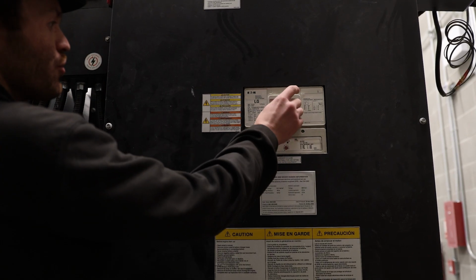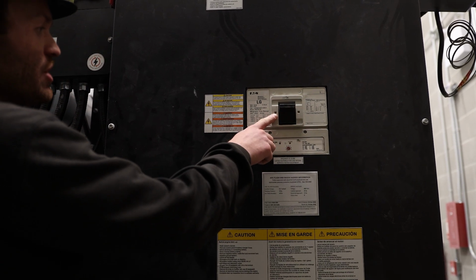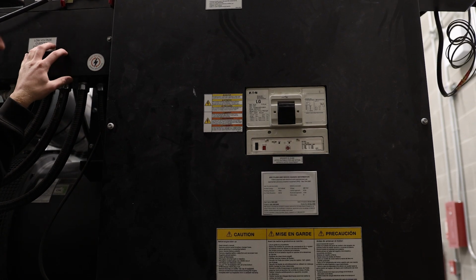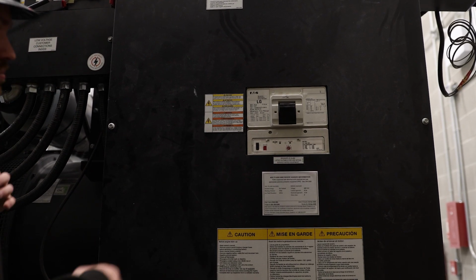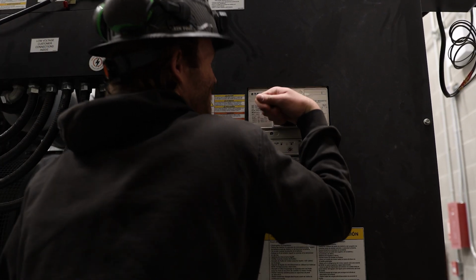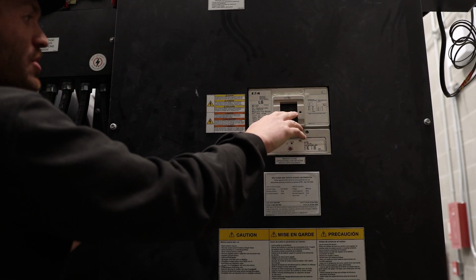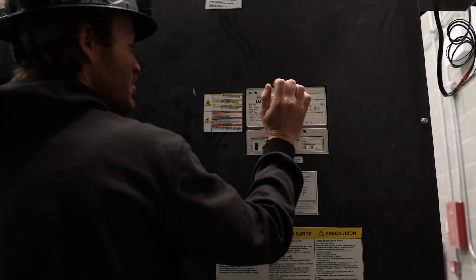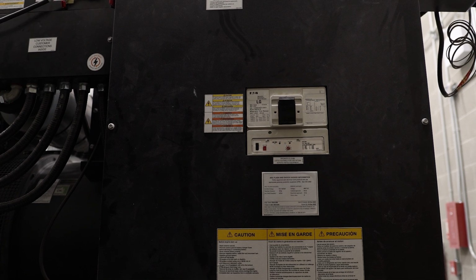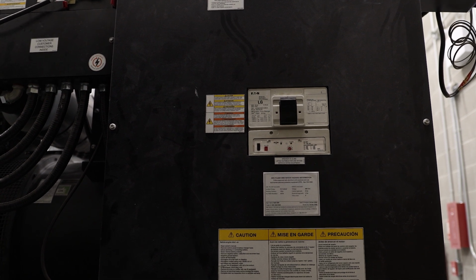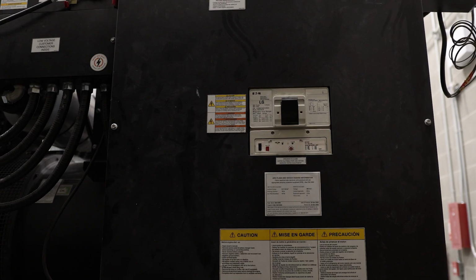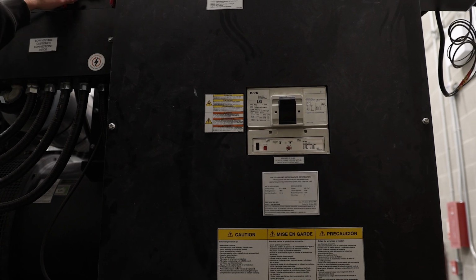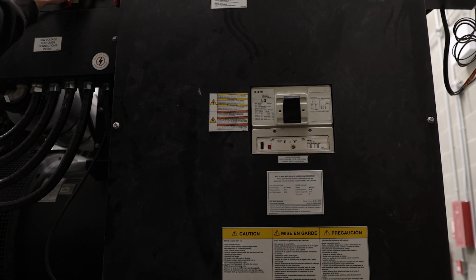Resetting the breaker, if it were to trip, it'll end up in about a halfway position. I recommend shutting down the generator beforehand, going down with it all the way to the off position, and once in the off position, go back up into on. It's pretty firm. You got to be very committed with it. You got to jam the thing apart, pretty much. And then we can clear my alarm on that.